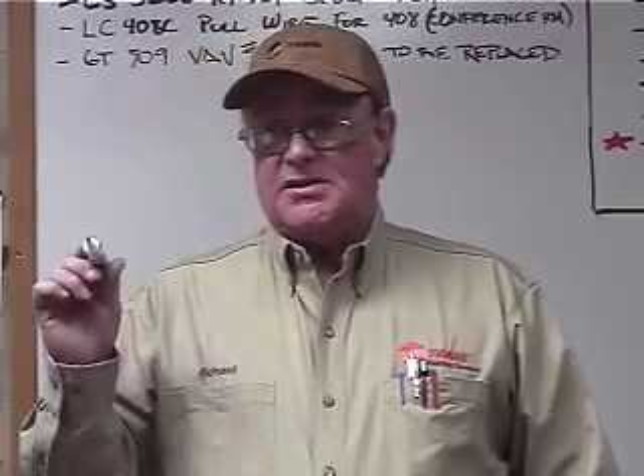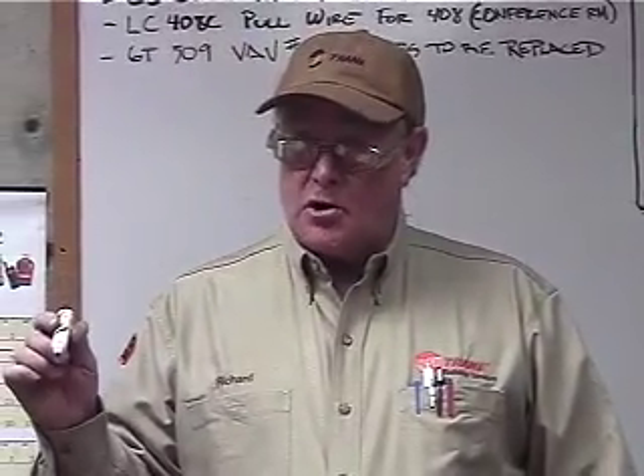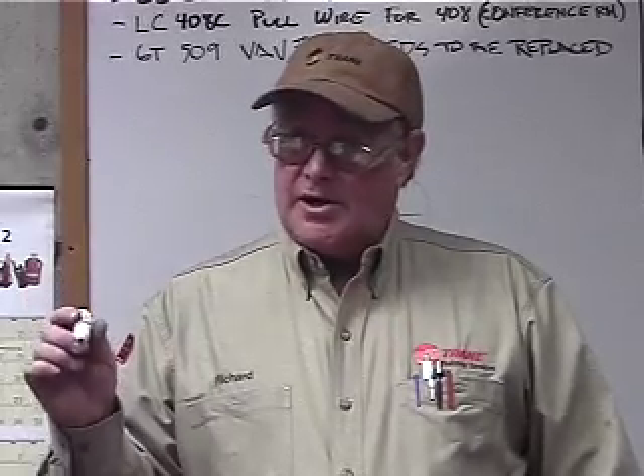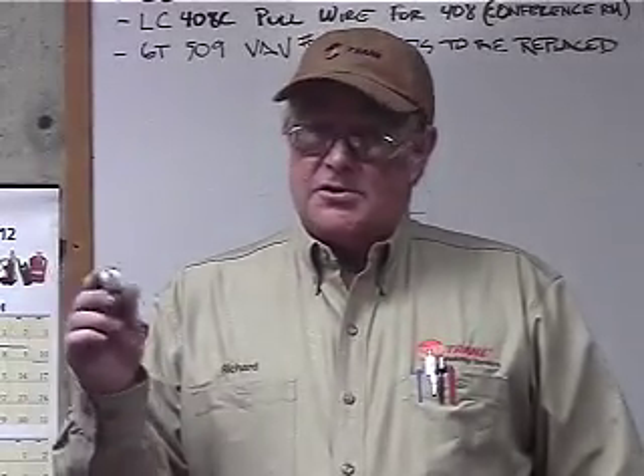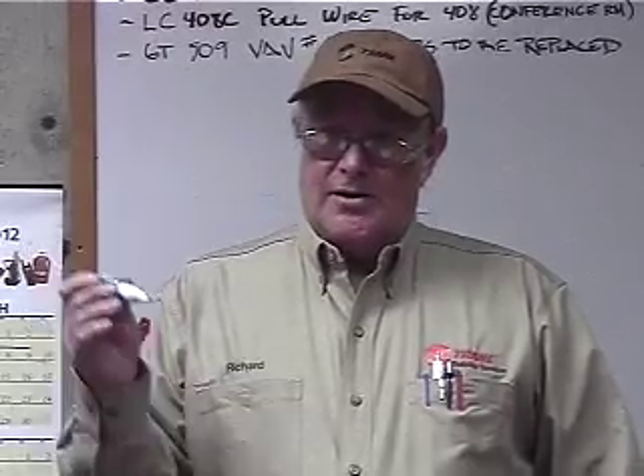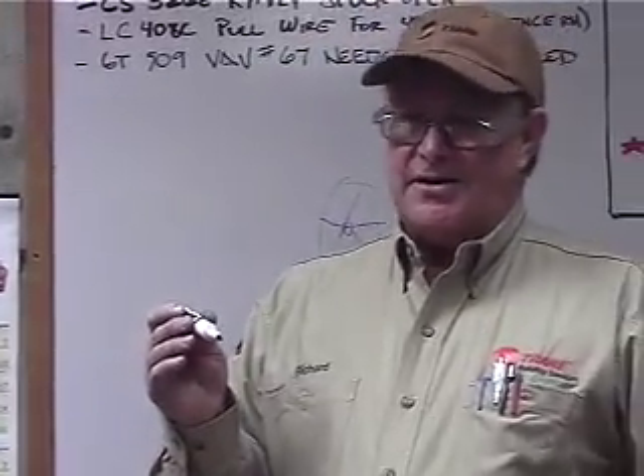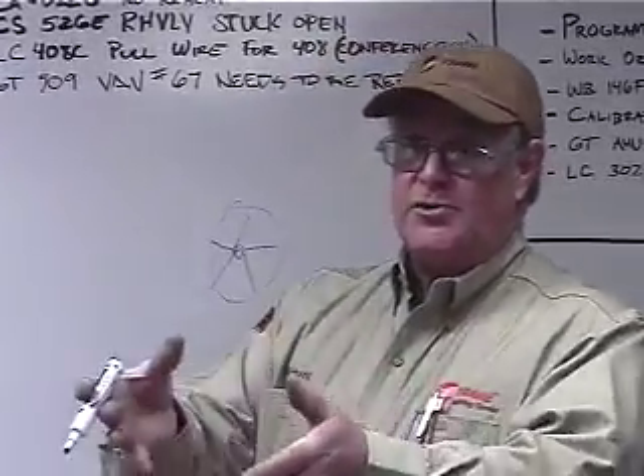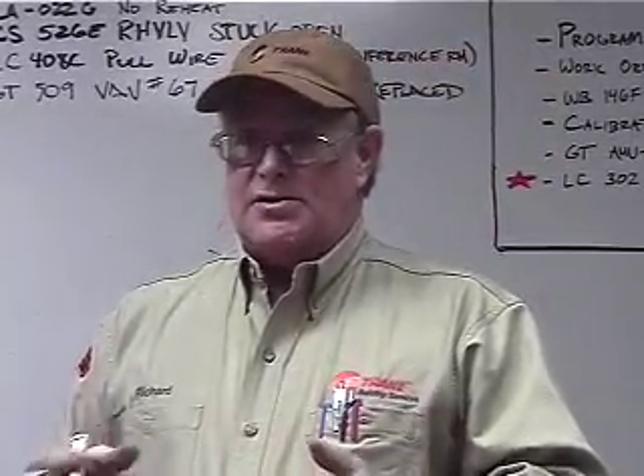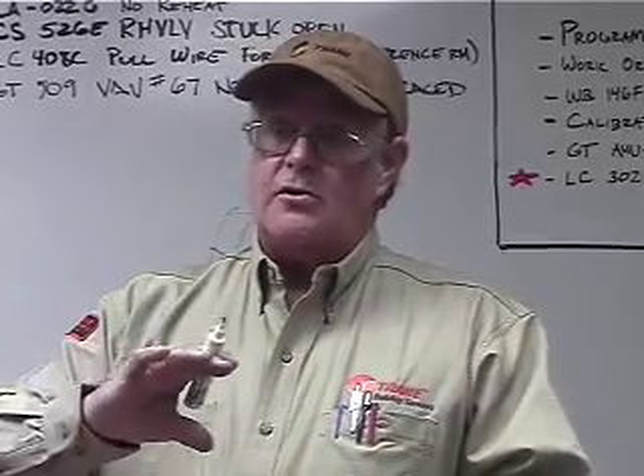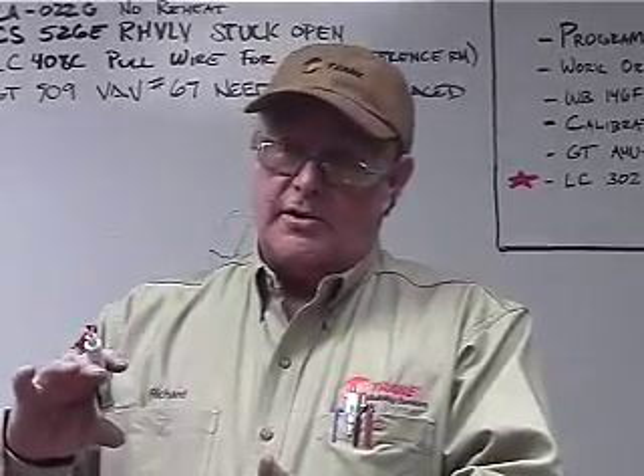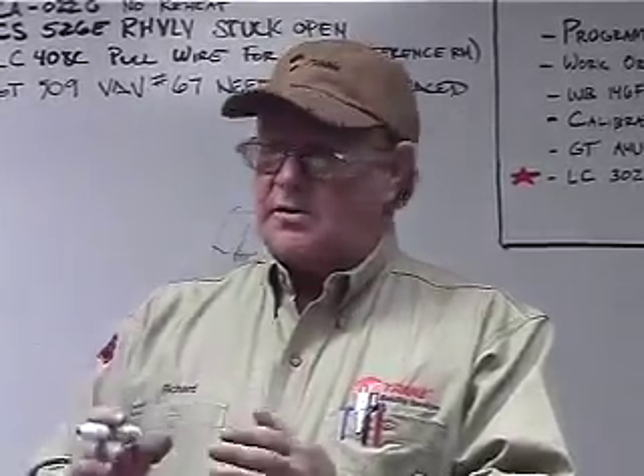What it does is it sees a capacity where the water temperature is warmer, and that's entering water temperature. So it goes through the controls saying, hey, at 200 tons capacity, I'm not making it. I need to open these vanes up and get more refrigerant going through the compressor to make it load up, so that the more refrigerant that's going through it, the harder the chiller's working and cooling the water down. So everything for load and unload is done with these inlet guide vanes.